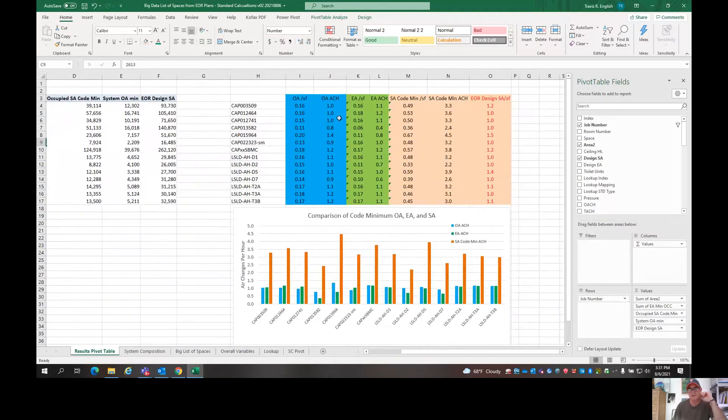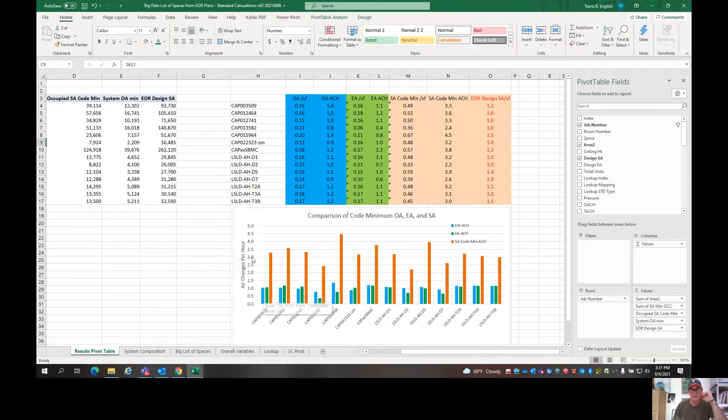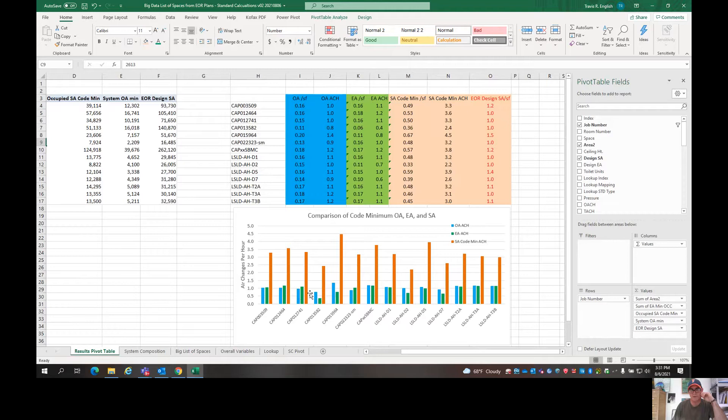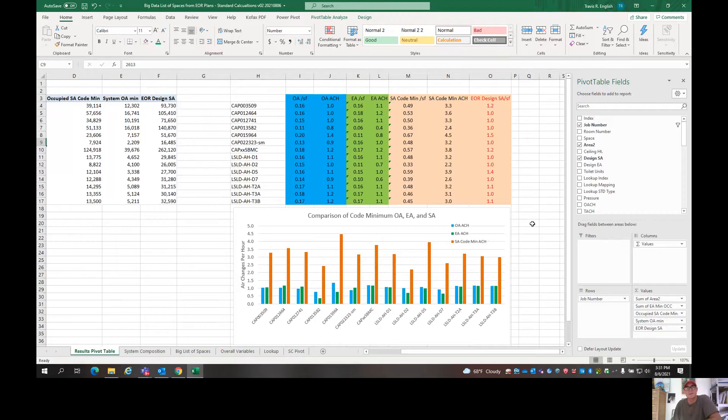So there's all the systems. Generally our outside air, this table here is in units of air changes. So you see our outside air riding around an air change 0.75 air change one air change right throughout these systems.